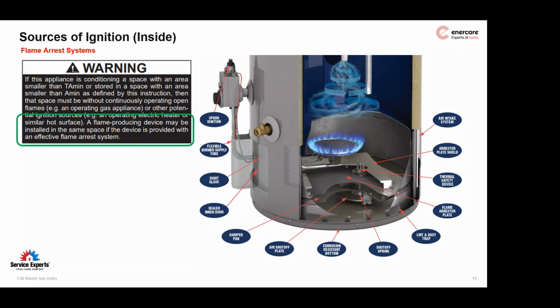So in or around 2003, FVIR or flame arrestor safety devices were required on tank type water heaters. So anything previous to 2003 may not be equipped with some sort of FVIR device, which means most of the water heaters we work with should already be equipped. Note the Rheem tank example, utilizing a few of these devices, like the arrestor plate in the bottom. The entire base of this unit has a plate in it that is actually an arrestor plate, and a spring-loaded combustion air shutoff plate, which is in the base as well, where combustion air is provided through. There's also that glass kind of flame arrest system.